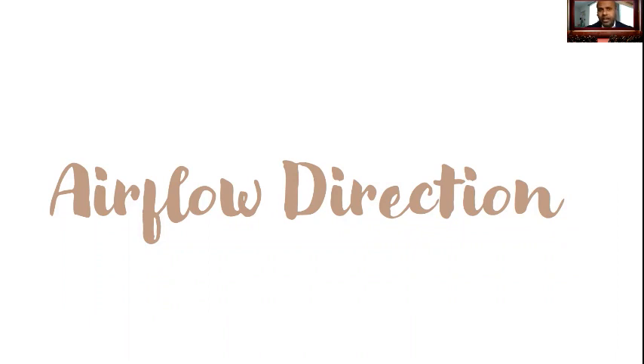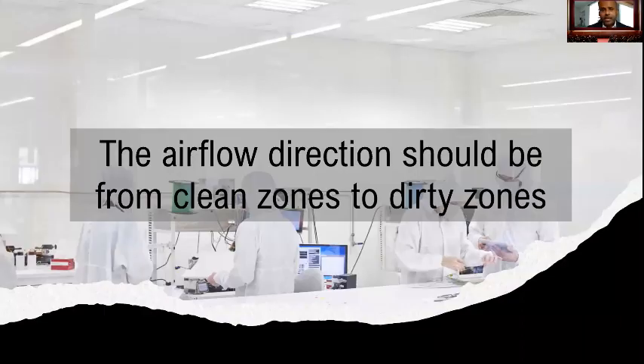Just like ventilation rate, airflow direction is another key element that influences airborne transmission of diseases. The airflow direction should always be from clean zones to dirty zones. Even in your homes and offices, direct the airflow of the fan so that it does not blow directly from one person to another.